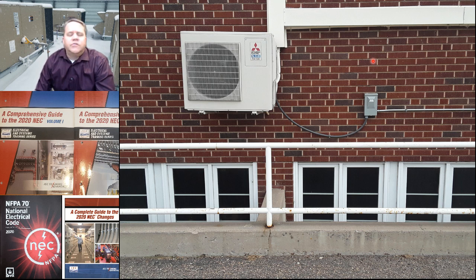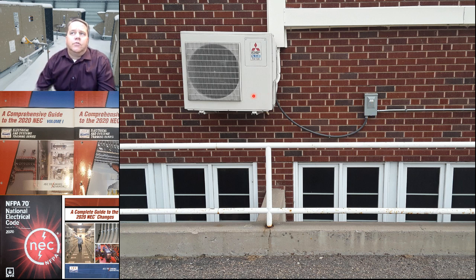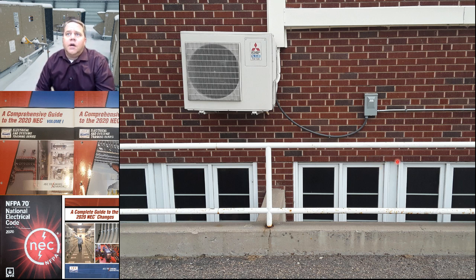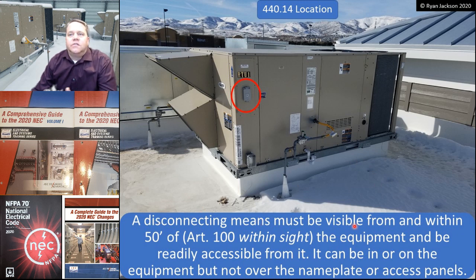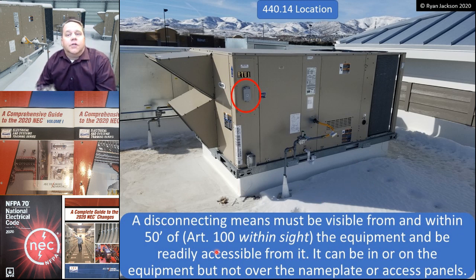The rules that regulate the disconnecting means for air conditioning equipment are a little bit different than the rules for disconnecting means for motors in 430.102 or transformers in 450.14. It's worded ever so slightly different, and it's worth talking about. When you look at 440.14, it says the disconnecting means has to be within sight of the equipment. And when you go to Article 100, within sight means visible and within 50 feet.